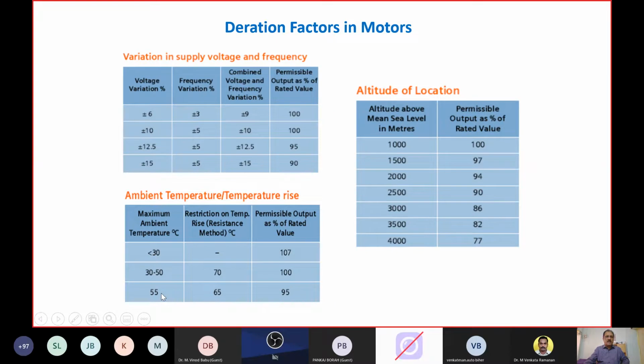Now you might ask, as per mathematical progression, we should also publish 60 degree, 65 degree, and so on. No, motor manufacturers caution that the motors are suitable for a combined temperature, including temperature rise, of about 65 plus 5, 70 plus 50, 120. So this is what they are recommending. With the hotspot allowance, another 10 degrees, 130 is permitted for class B rise. So beyond this, not only the temperature rise of the motor, but also the performance of grease and bearings have to be considered. Therefore, the motor manufacturers clearly indicate that for any ambient temperature beyond 55, motor manufacturers should get involved in designing a motor with adequate cover and protection and give it to you. Therefore, any derating for temperature or temperature rise should be limited up to 55 degree ambient.